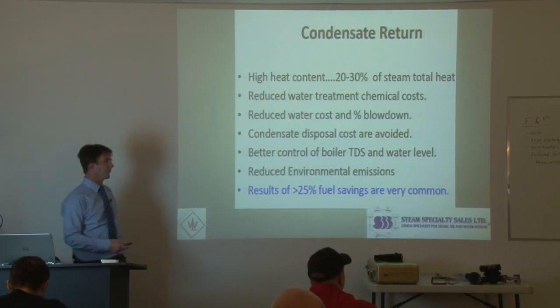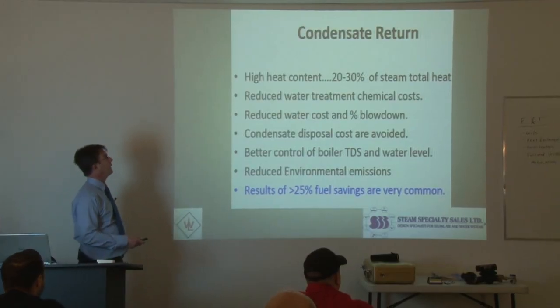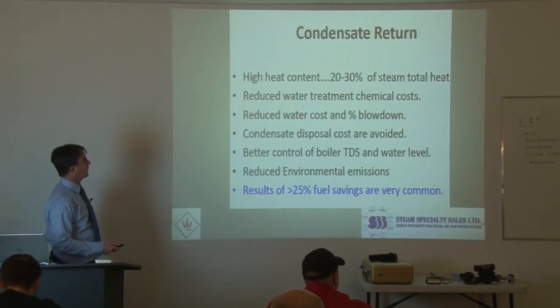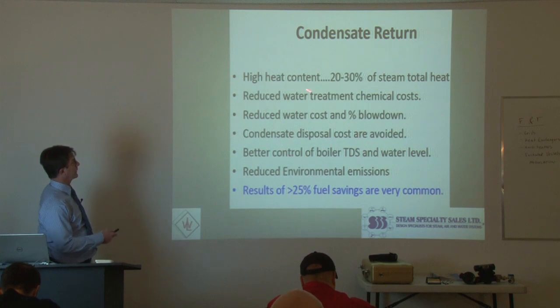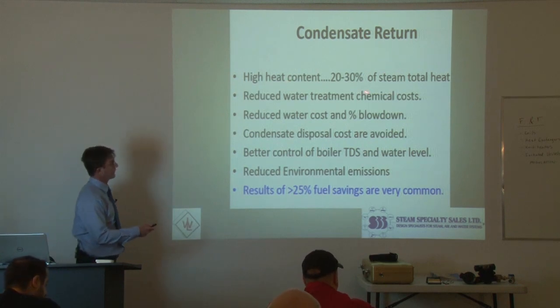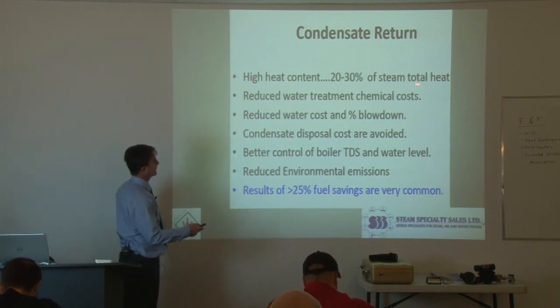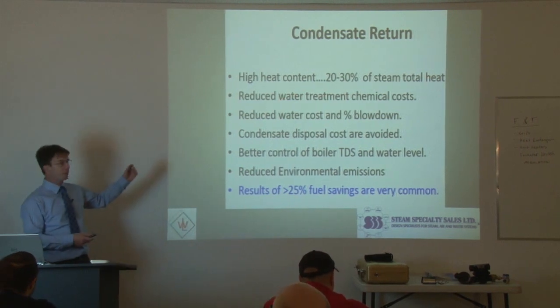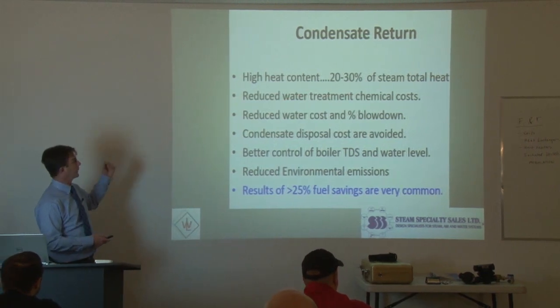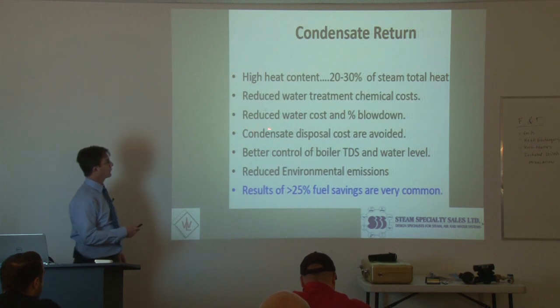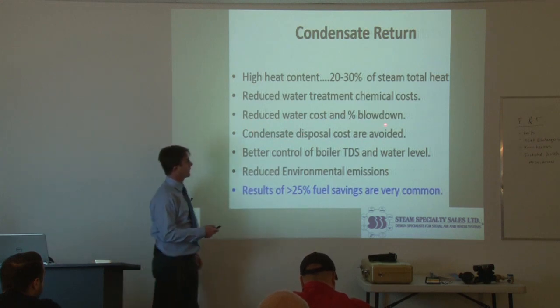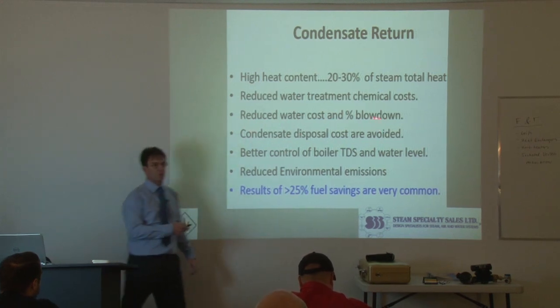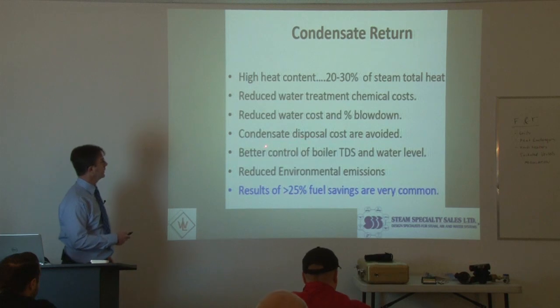Now we're going to move on to condensate return. Why do we want to return condensate? It has a high heat content - 20 to 30% of the steam's total heat. We want to reduce water treatment chemical costs, reduce water costs, and reduce the percentage of blowdown in our boilers.